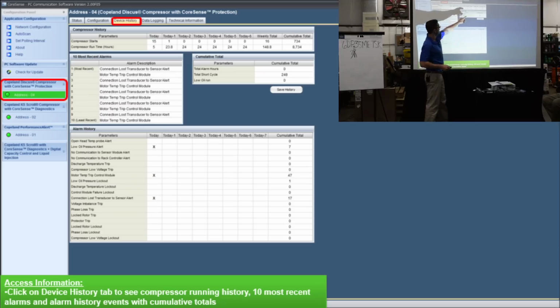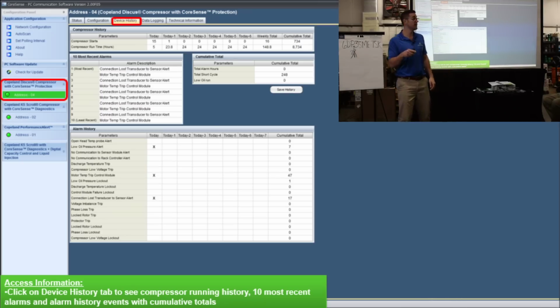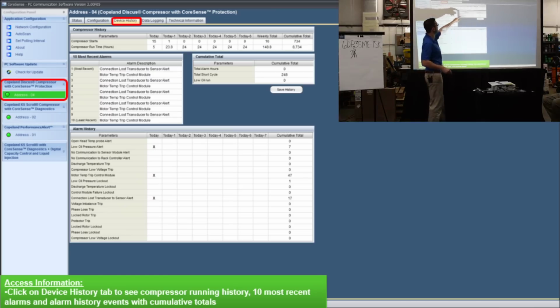Like right here, this compressor ran for over 8,000 hours and it started 732 times. Is that valuable as a technician? That's really valuable. And then it tells you, look, 24 hours it ran. How many times did it start that day? 0, because it's full running. Look, all of a sudden it's running.